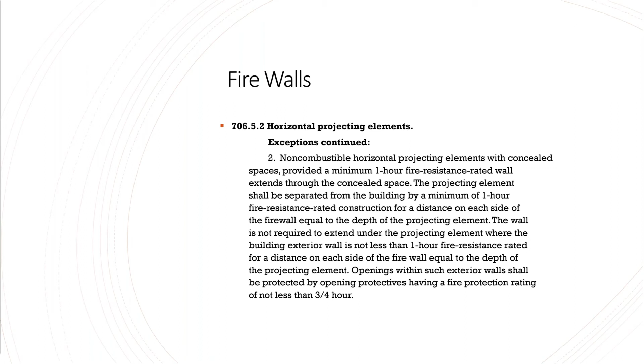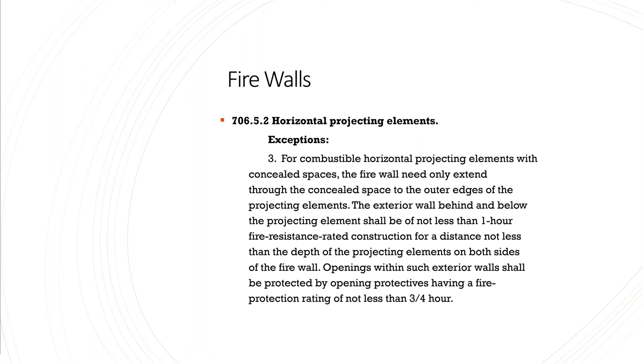And exception number 3, and I'll give you visuals to help too, but for exception number 3, for combustible horizontal projecting elements with concealed spaces, the firewall need only extend through the concealed space to the outer edge of the projecting element. The exterior wall behind and below the projecting element shall be of not less than 1 hour fire resistance rated construction for a distance not less than the depth of the projecting elements on both sides of the firewall. Openings within such exterior walls shall be protected by opening protectives having a fire protection rating of not less than 3/4 hours. So what did I just say? There's a lot to that.